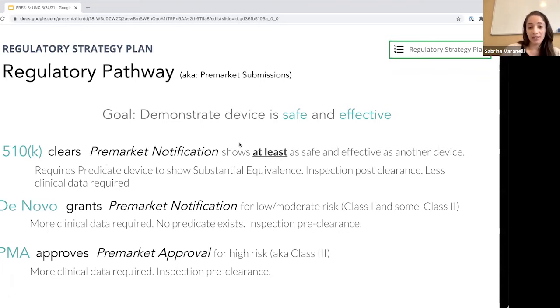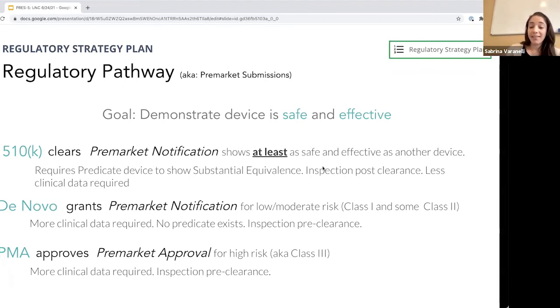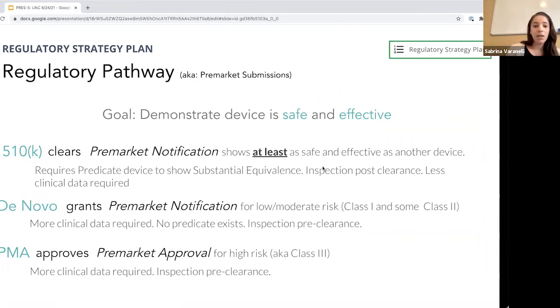With a 510k clearance, you're demonstrating that your device is at least as safe and effective as another device already on the market. You may have heard the term 'predicate device' — that's a device with a similar intended use that you use as the benchmark for your clinical and safety testing. You select predicates not just based on technology, but on how the technology is used to perform the intended use. Selecting your predicate device is something we recommend you get assistance with.